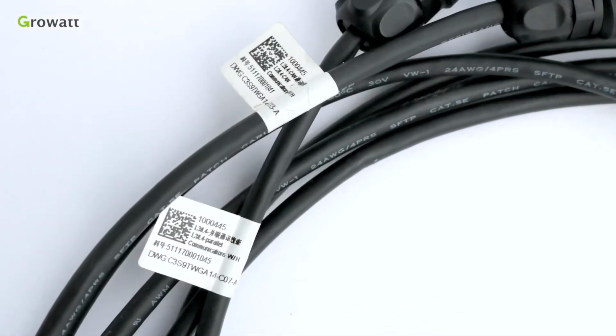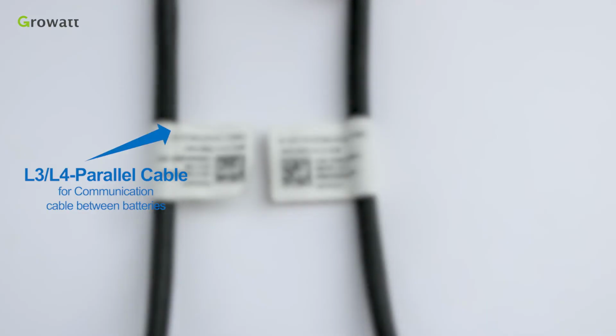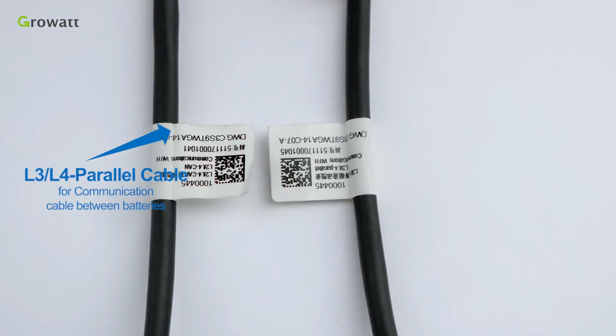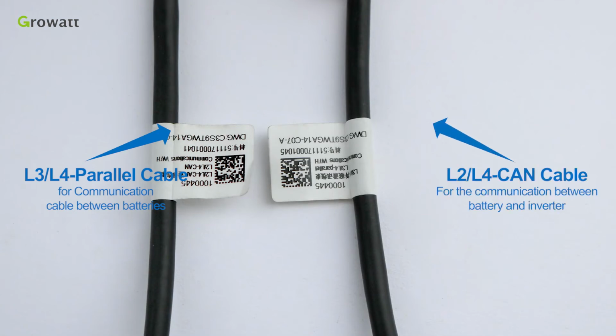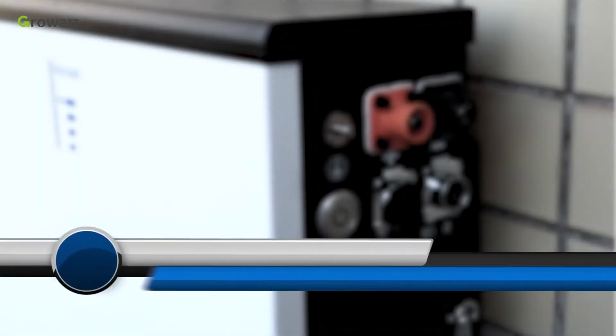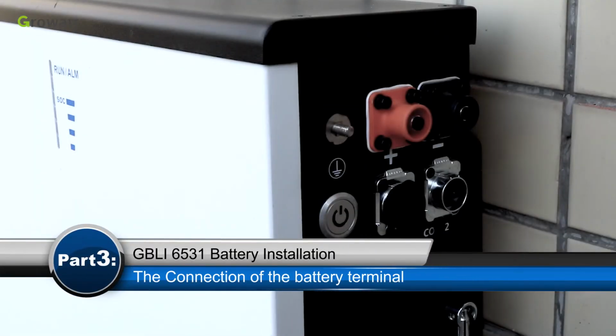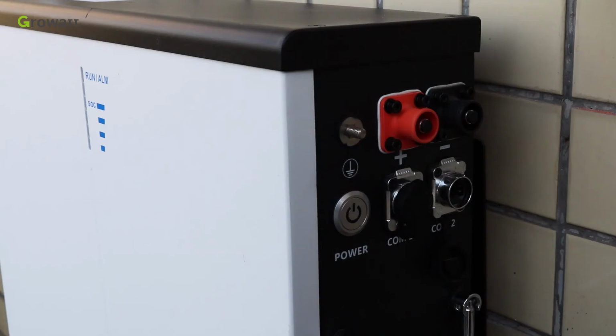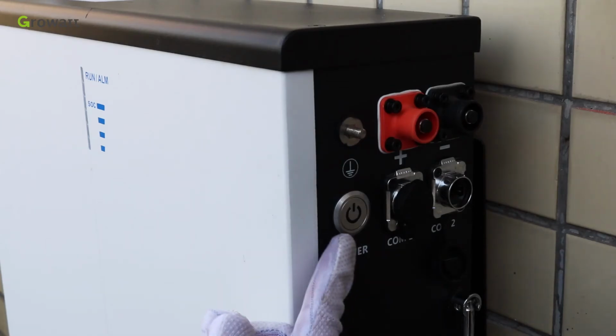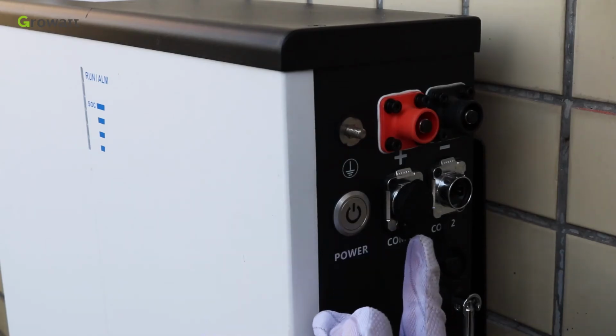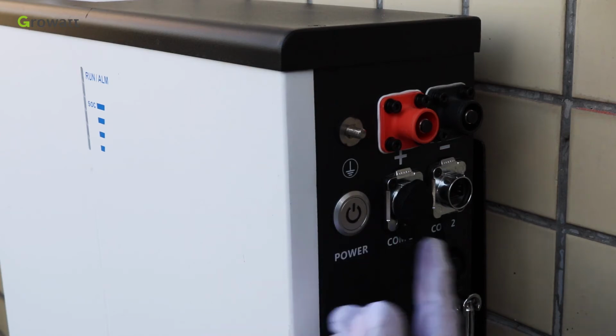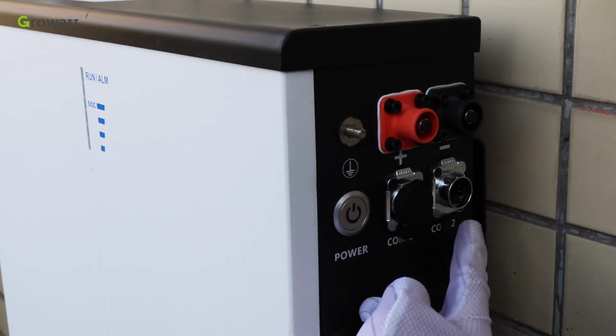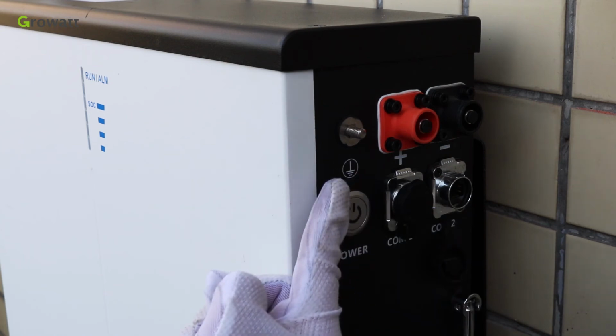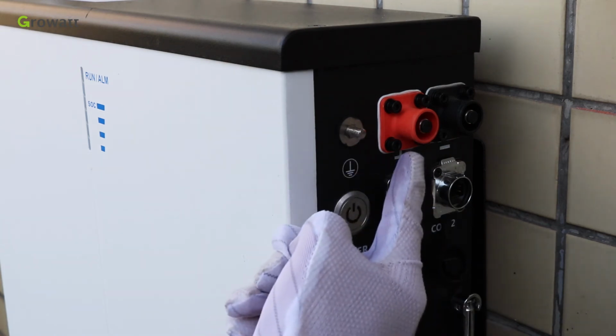Pay attention to the communication cable. Cable with L3-L4 parallel label is for the communication between batteries. Cable with L2-L4 CAN label is for the communication between battery and inverter. There is the button to power on and off the battery. COM.1 communication terminal from battery to the inverter.